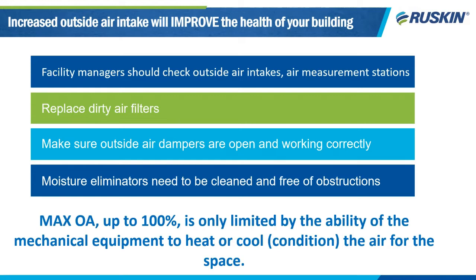So facility managers should be checking their outside air intakes, making sure their air measurement stations are working correctly. They should replace dirty air filters. They should make sure that the outside air dampers are open and working correctly. Moisture eliminators need to be cleaned and free of any obstructions. The maximum amount of outside air is limited only by the ability of the heating and cooling system to keep the humidity and temperature inside of the building under control.